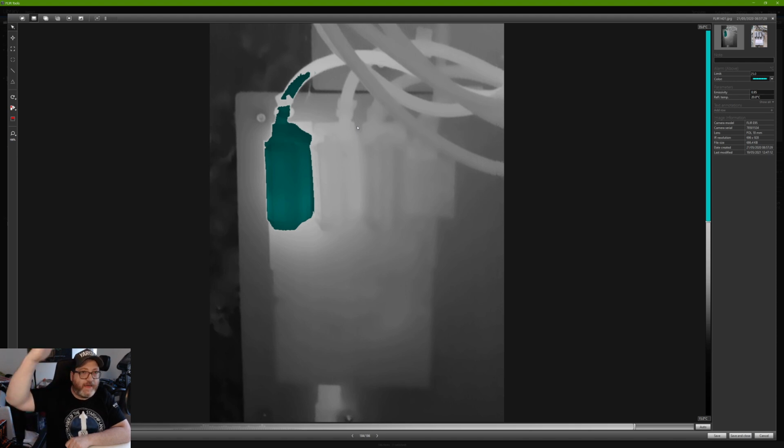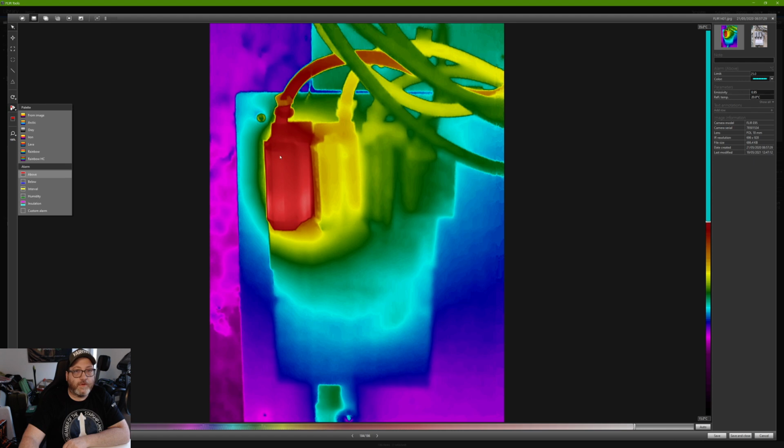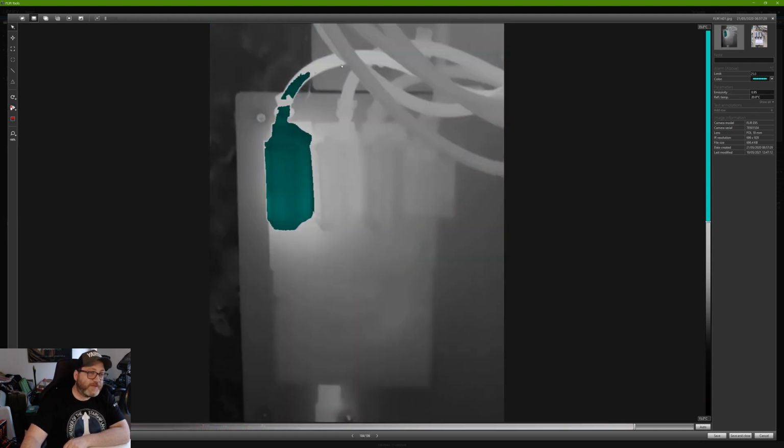That's a higher than, and I've done that with a few places where I'd have equipment with a high surface temperature, and I'd set the surface temperature to 80 degrees or 70 degrees, and then I'd just blend the rest of the image out. So like this, you can see this is an example where, of the palette options, gray is best working with alarms. It really is best working with your alarms in this case. So that's a high alarm.